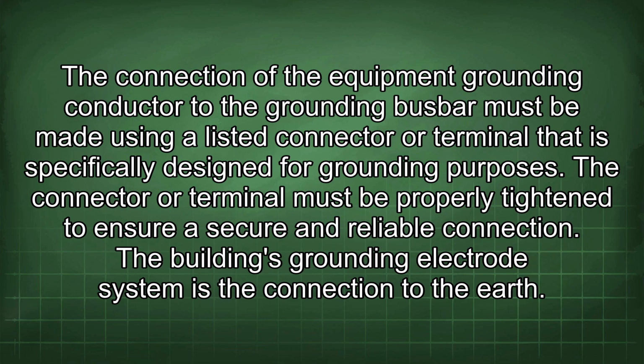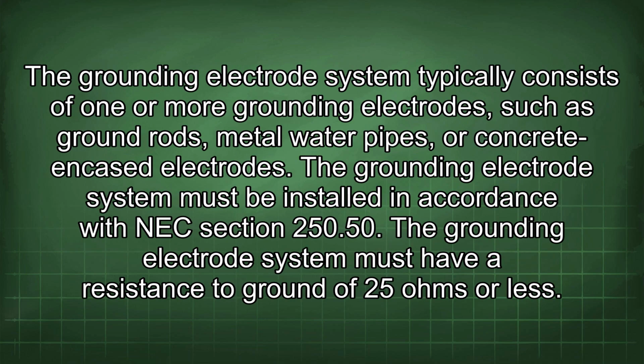The building's grounding electrode system is the connection to the earth. The grounding electrode system typically consists of one or more grounding electrodes, such as ground rods, metal water pipes, or concrete encased electrodes. The grounding electrode system must be installed in accordance with NEC section 250.50. The grounding electrode system must have a resistance to ground of 25 ohms or less.